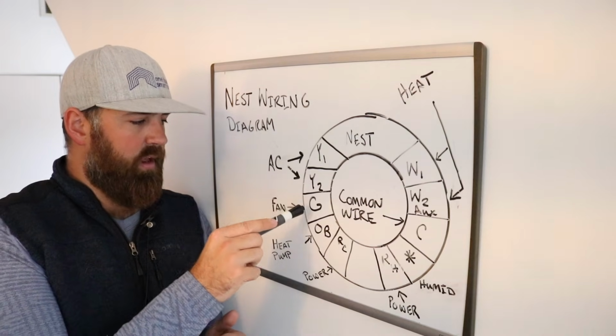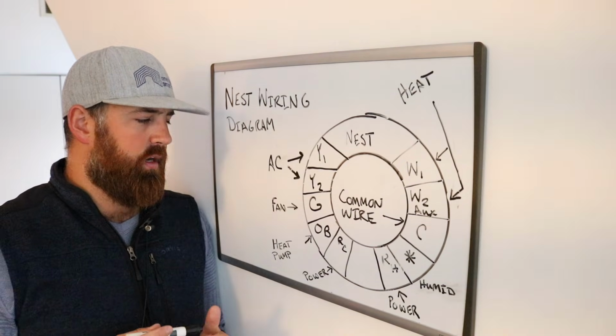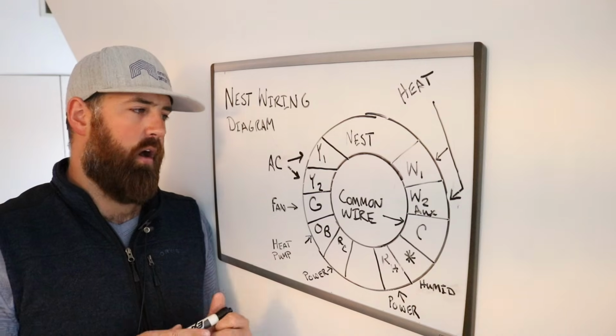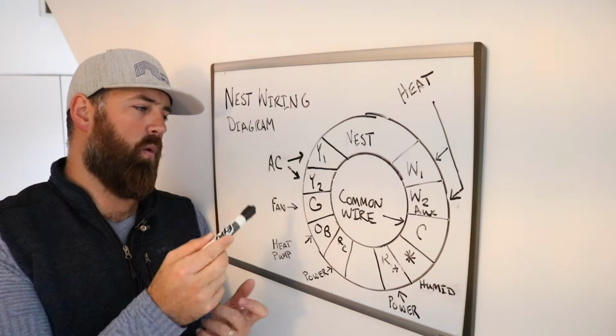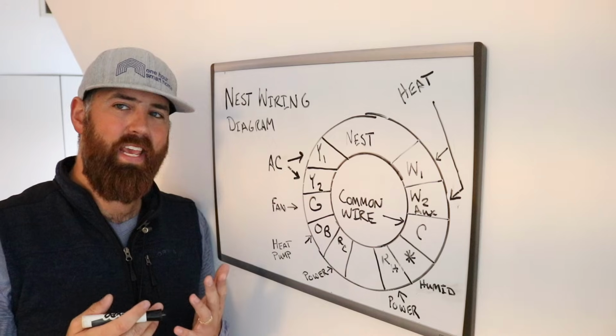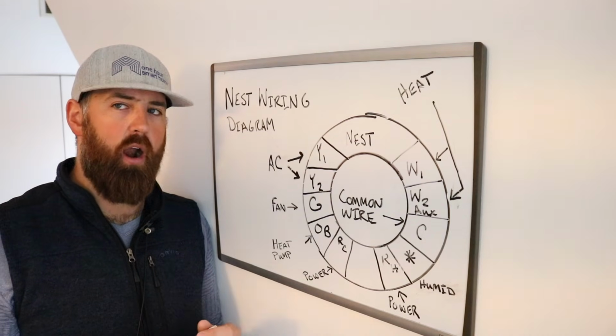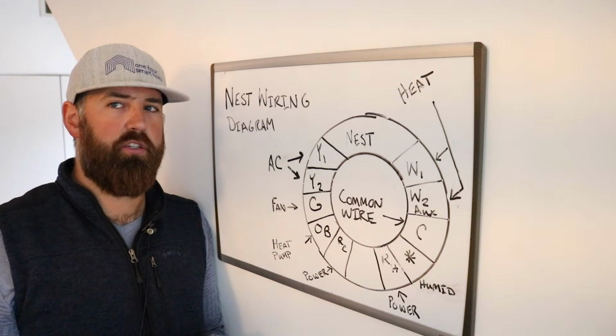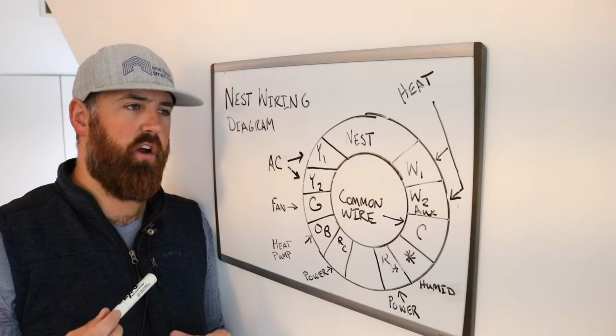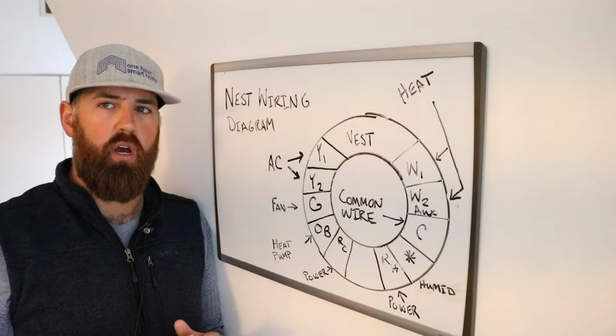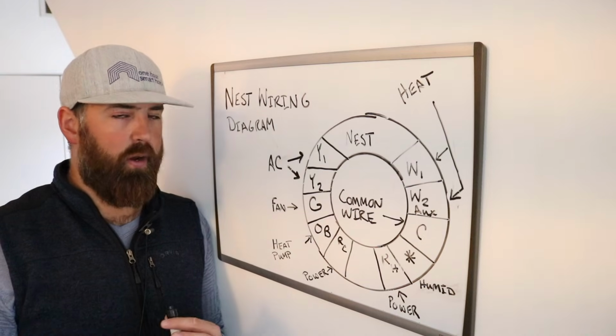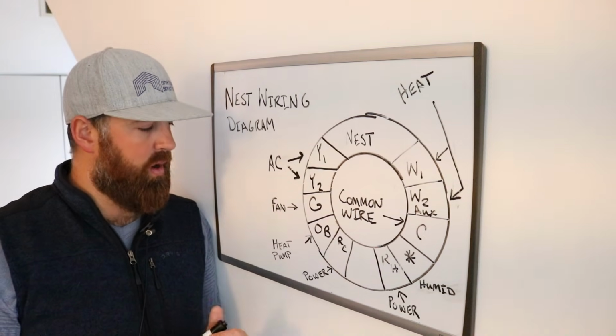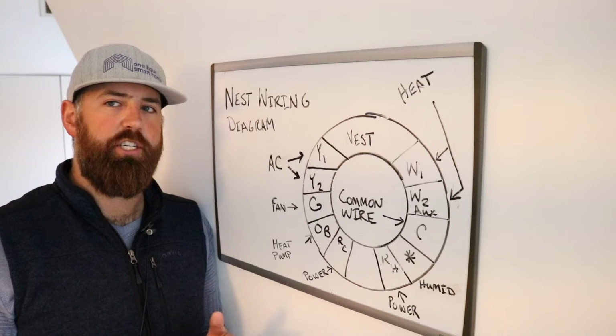Now, fan, that is the G wire. The G wire is typically a green wire. And before we go on, Y1/Y2 is typically a yellow wire, but not always. If your HVAC contractor followed the standard color conventions, they would have used a yellow wire for Y1, but that's not always the case—some people don't do that. The fan wire is typically the G wire.